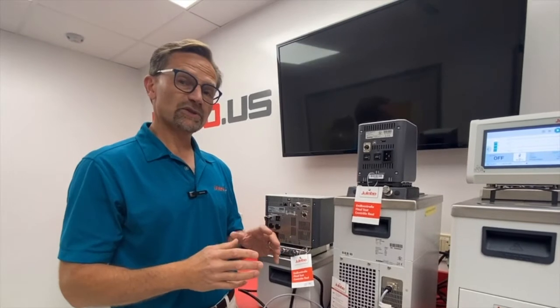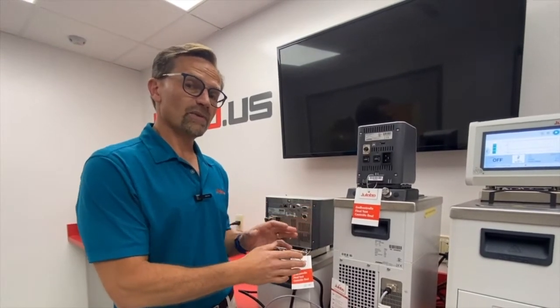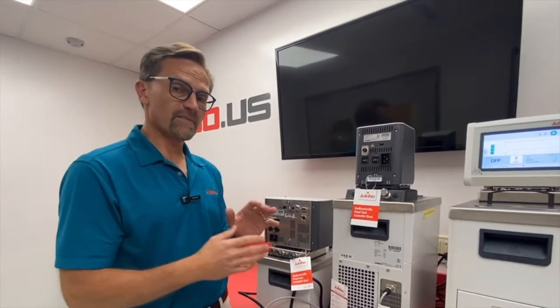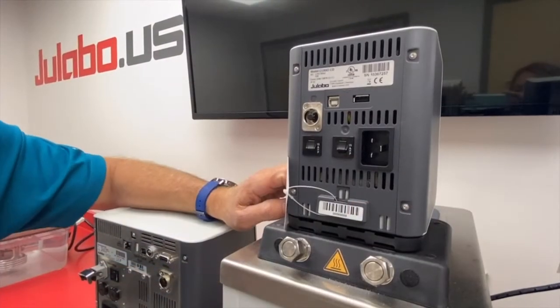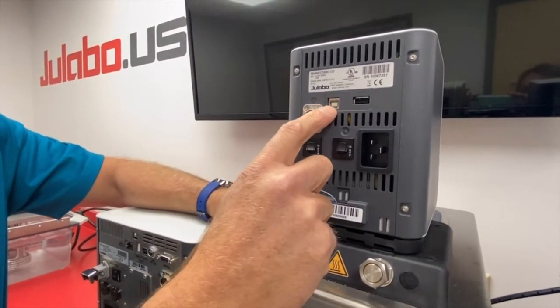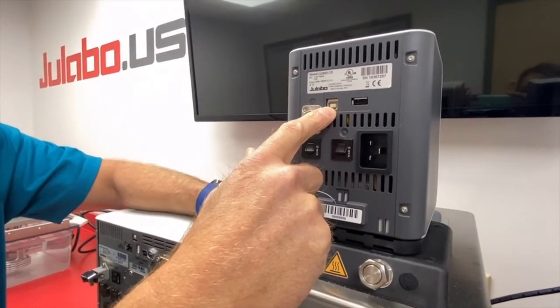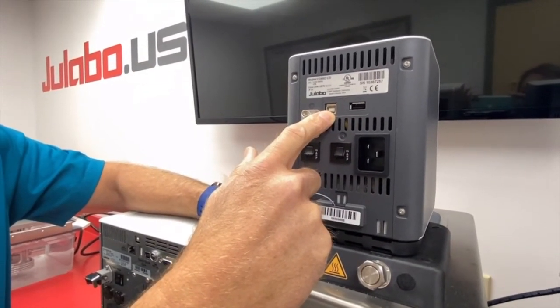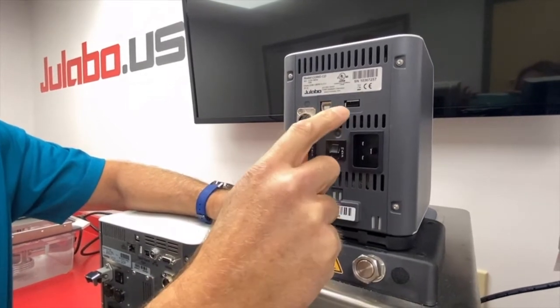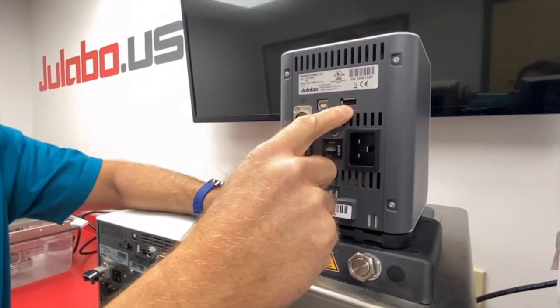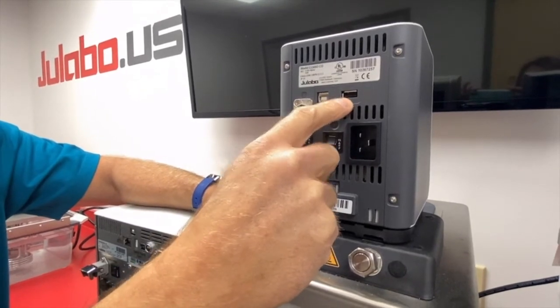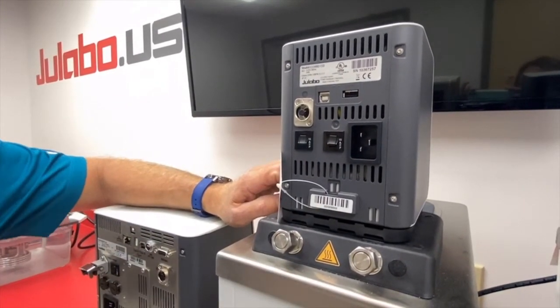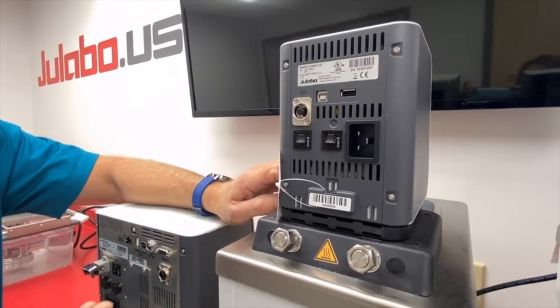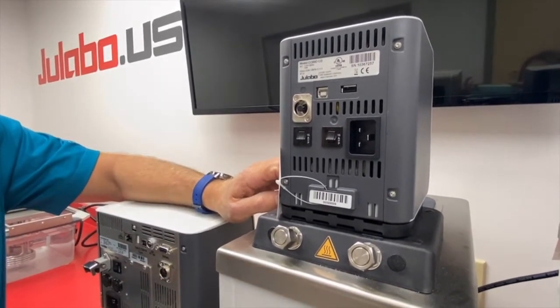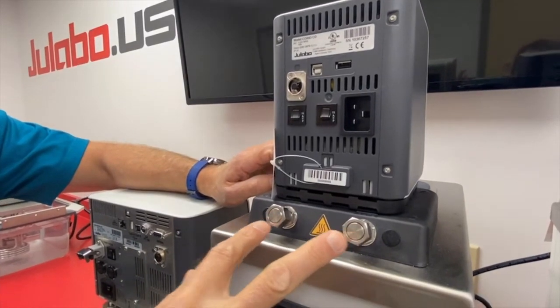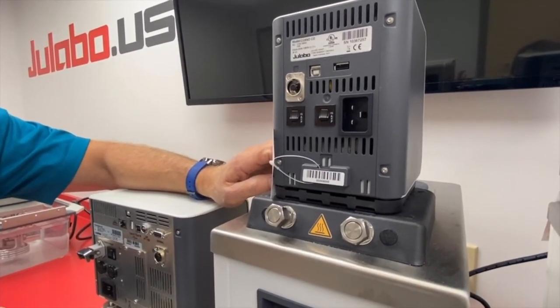Okay, so here's a comparison of the CORIO CD products with the MAGIO products. So we have the back of the units. On the back of the CORIO CD model, you have the USB-B port. This is the position used for communication to an external PC for remote control, and a USB-A slot. This is used for data logging, time temperature information, also for black box service data, in addition to any firmware updates that might come from the field. And on the back down below, you have your M16 male threaded fittings for the pump inlet and outlet.